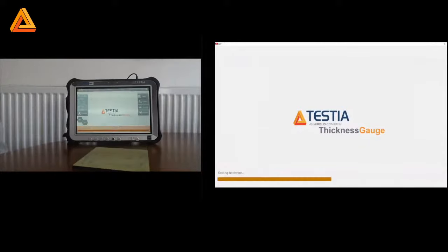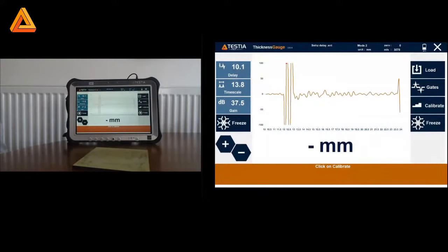The thickness gauge has a far more reduced capacity than the flaw detector is capable of. The reason being is that because we can set up the thickness gauge inspection data and calibrations in the UT mode, we wanted to not have as many features available on the thickness gauge, so that it is a quicker and faster module to work with.